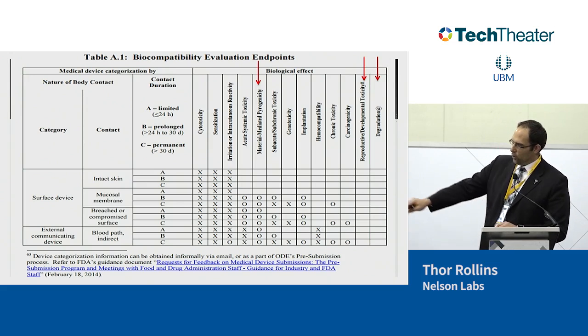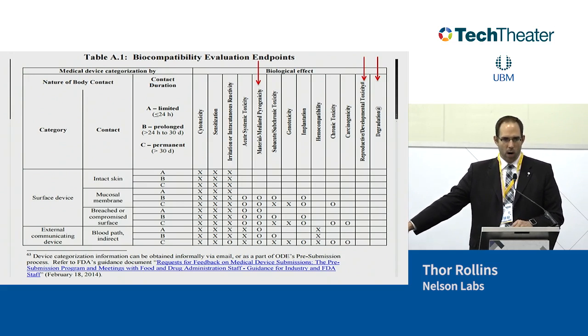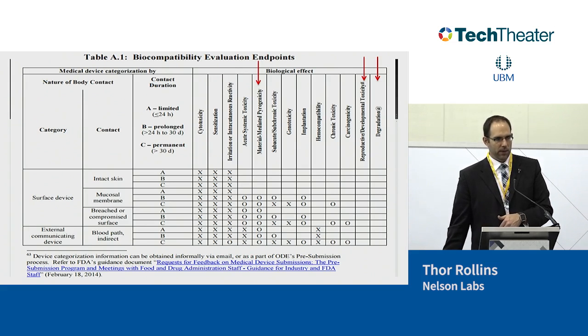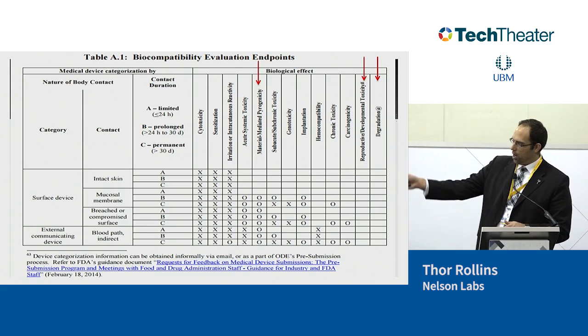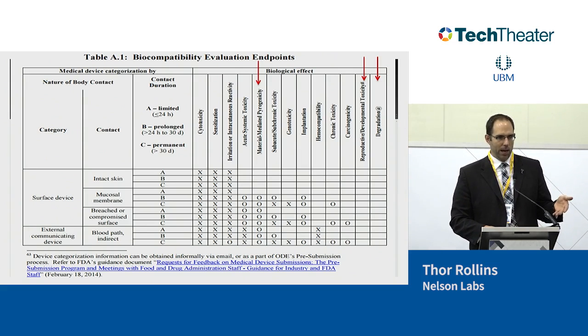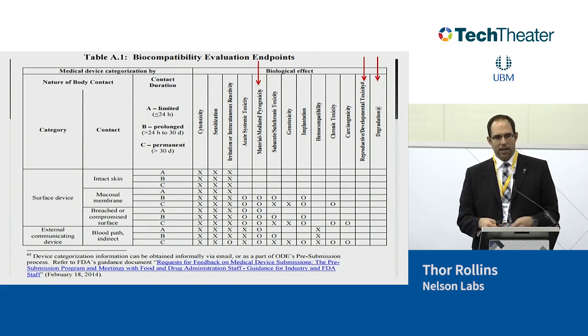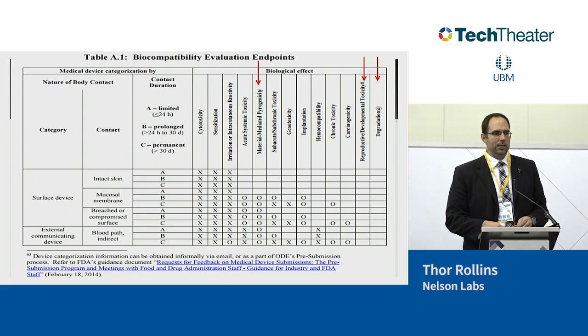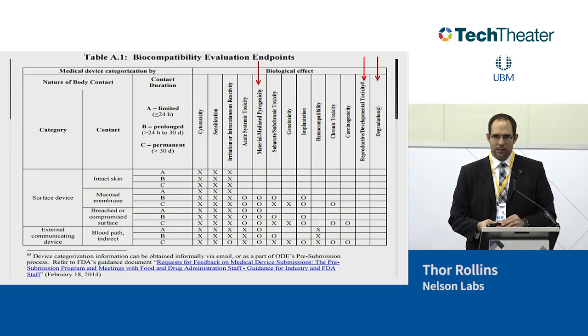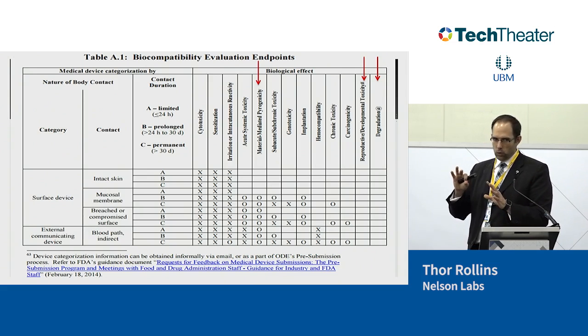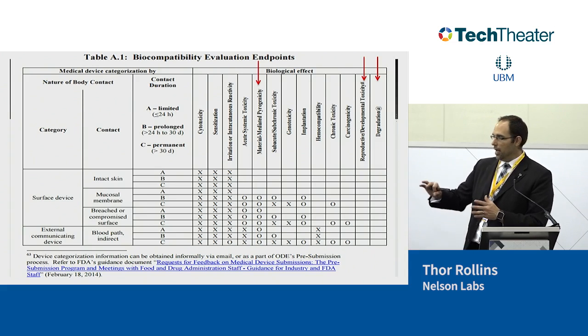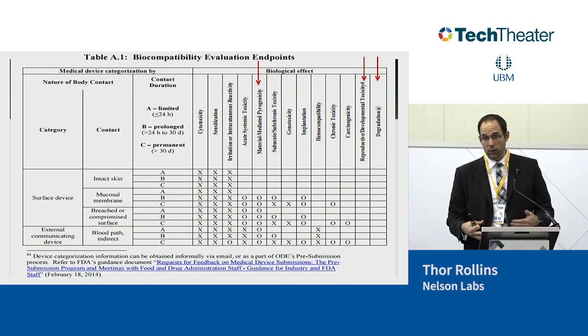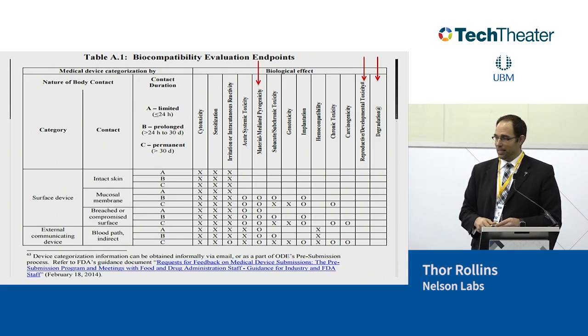Before, we kind of assumed that if you had acute systemic tox marked, you may want to look at material-mediated pyrogen. The FDA now has put a whole new column in there where it talks about you have to do material-mediated pyrogen or assess it if you have that category marked. They also put emphasis on reproductive toxicology and degradation tests. They do say that you only have to do these tests if you think your device has a risk of these two endpoints. Okay? So if you don't have a risk of degradation or reproductive toxicity, then you don't have to worry about those endpoints. But if you think you do, talk to us because we may have to assess those.